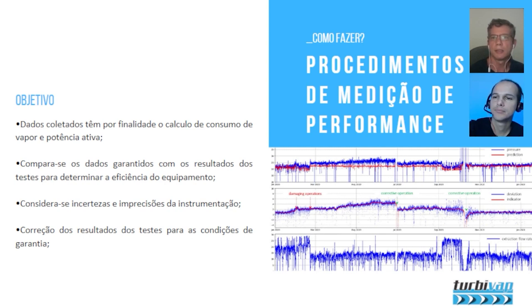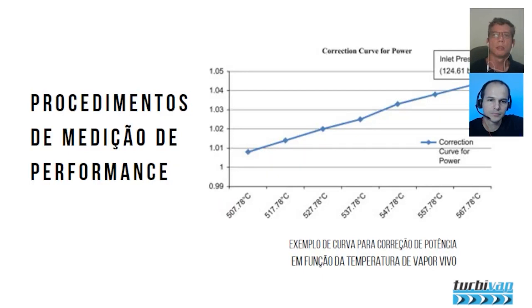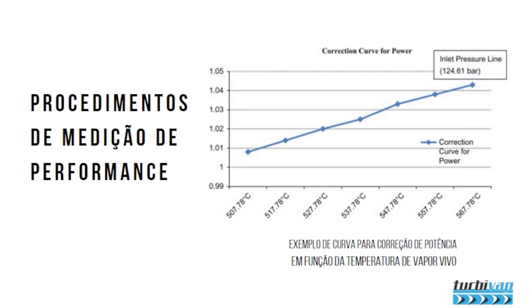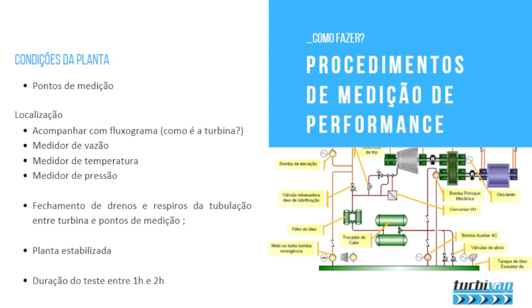Test results are corrected to warranty conditions. For example, if steam is designed at 500°C but at the time of testing the temperature was 515°C, this is accounted for so there is no harm to either party. Here is an example of a temperature correction curve for a given pressure — the graph ranges from 507°C to 567°C, and the correction factor on the Y-axis is applied to the final power calculated at the time of test execution.